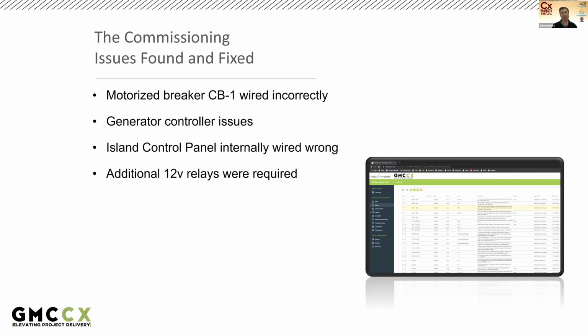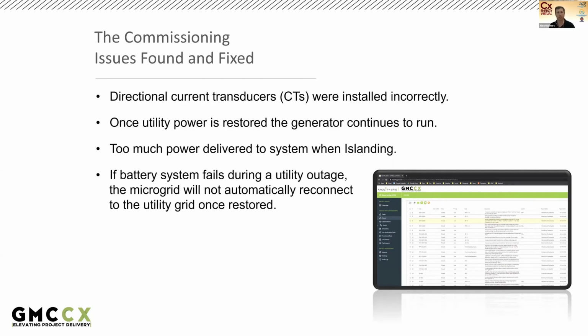Third item, the island control panel was internally wired wrong, which led to additional 12-volt relays needing to be installed to properly work with the motorized breakers and the generator controller. The motorized breakers' interlock needs to be hardwired so the system can't export generator power to the grid. Directional electrical meter current transducers, or CTs, we found were installed incorrectly. It was a simple fix, but they were just installed in the wrong direction. They had to be turned around so they were in the correct direction.